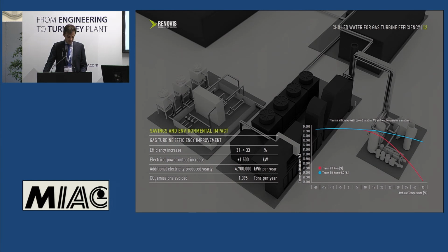We are therefore able to obtain from the gas turbine an additional power of more or less 1,500 kilowatts of electrical power from the cogeneration system, of course, even during the summer season, of course, if compared to the absence of a cooling coil system in the inlet air chamber.